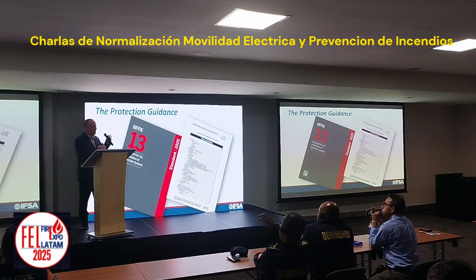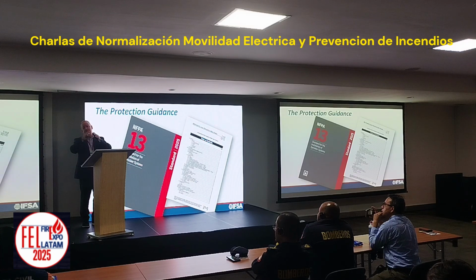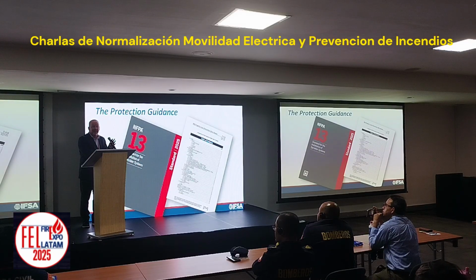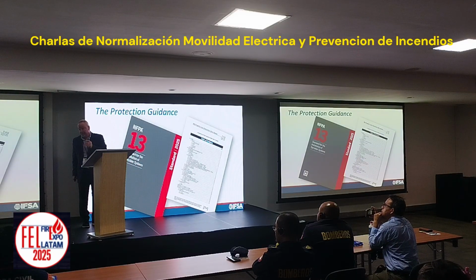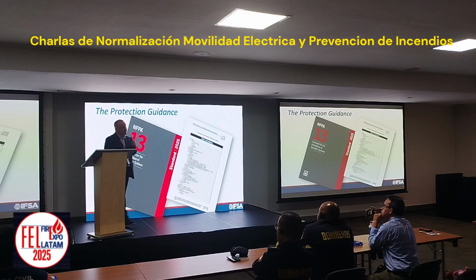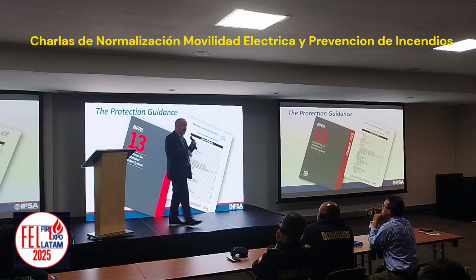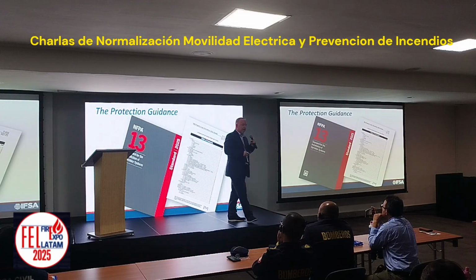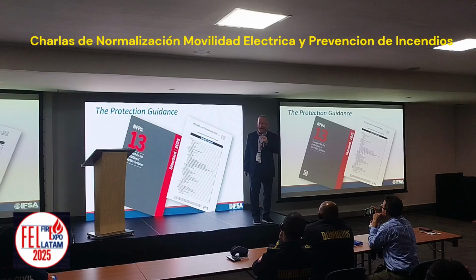Well, in the U.S., and I'm sure you're familiar with this document here in Colombia, mainly because for about 4 or 5 years I was down here teaching this topic. So we know about it, NFPA 13. But it says nothing about protecting lithium-ion batteries. As a matter of fact, it has a section in the annex of the standard that says this standard does not cover the protection of lithium-ion batteries.